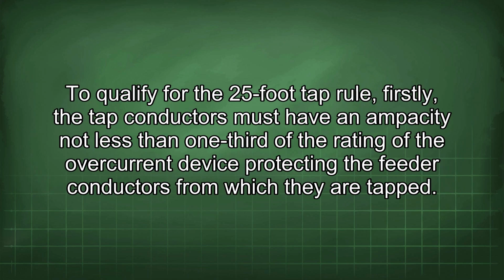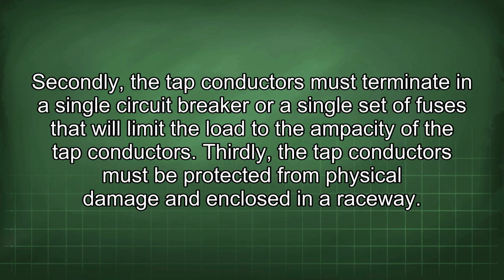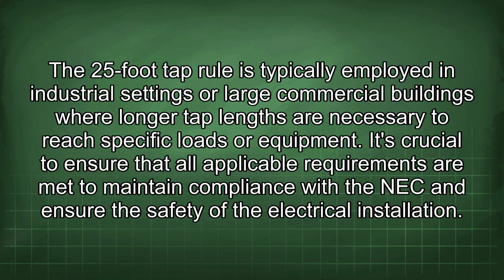To qualify for the 25-foot tap rule, firstly, the tap conductors must have an ampacity not less than 1/3 of the rating of the overcurrent device protecting the feeder conductors from which they are tapped. Secondly, the tap conductors must terminate in a single circuit breaker or a single set of fuses that will limit the load to the ampacity of the tap conductors. Thirdly, the tap conductors must be protected from physical damage and enclosed in a raceway. The 25-foot tap rule is typically employed in industrial settings or large commercial buildings where longer tap lengths are necessary to reach specific loads or equipment.